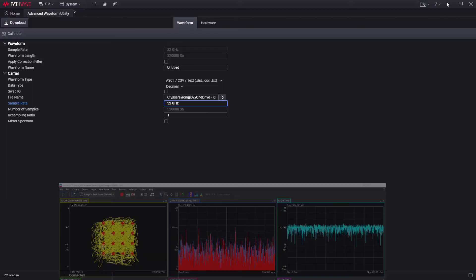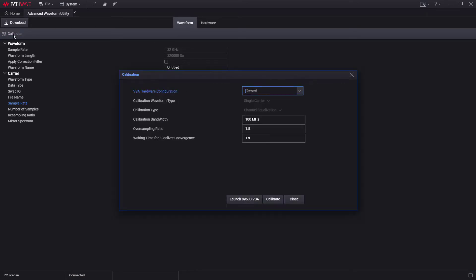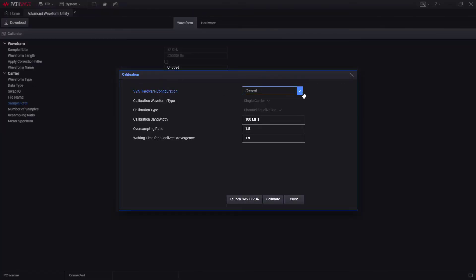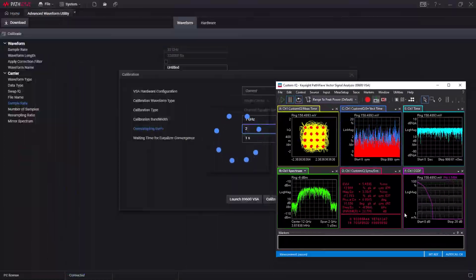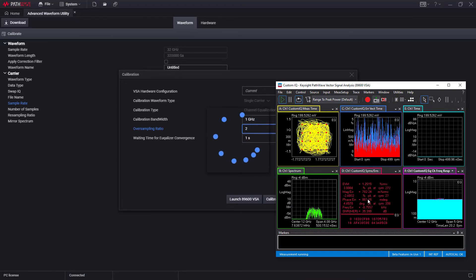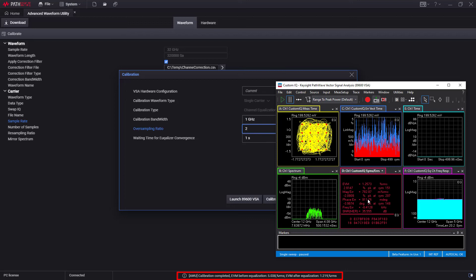Let's go back to the PathWave Signal Generation software and press the Calibrate button in the Calibration window. Because we have already launched VSA, keep the default setting. Then we need to modify the calibration bandwidth to 1 GHz and over-sampling ratio to 2. The waiting time for equalizer convergence of 1 second looks good, so keep it. Then press the Calibrate button. The calibration of channel correction will automatically start — it may take some time. Once completed, you can see a message pop up at the bottom bar: Calibration completed. EVM before equalization: 5.038%. EVM after equalization: 1.216%.